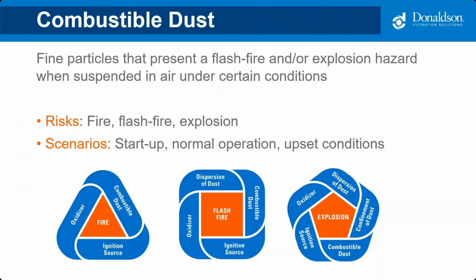Another thing, as Chris mentioned earlier, the dust generated during the battery manufacturing process may be combustible and pose a fire, flash fire, or explosion risk. Most of us are familiar with the fire triangle shown here. You've got fuel, oxygen, and a source of ignition, and you have everything necessary for a fire. When that fuel, in this case our dust, is dispersed in the manufacturing process, it can lead to flash fires.